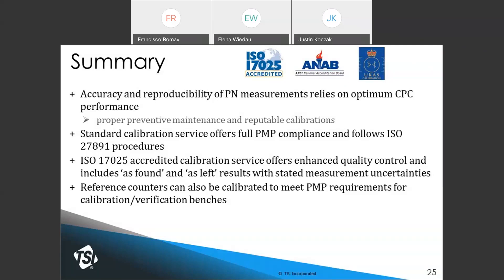Regarding the normalized plateau correction in the slides: the normalization brings counting efficiency to exactly 100% at the plateau, but CPCs are not perfect. Counting efficiency at the flat part of the curve is close to 100% but typically 97–98%. The normalized efficiency curve is not actually used in calculations; the actual calibration curve for the reference CPC is used.